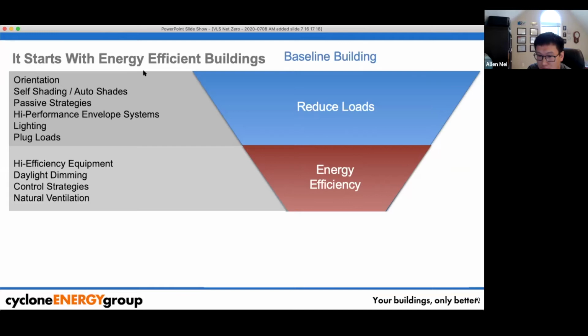Also, a lot of certification programs and the energy code require daylighting controls, not just from a comfort perspective but also energy efficiency. We oftentimes see daylight harvesting in office type spaces, which reduces a lot of lighting usage. Speaking of control strategies, in the past some controls were optional, but today demand control ventilation, shut off controls, and VFD controls are, in a lot of cases, mandatory in the energy code. Natural ventilation is a great passive design.